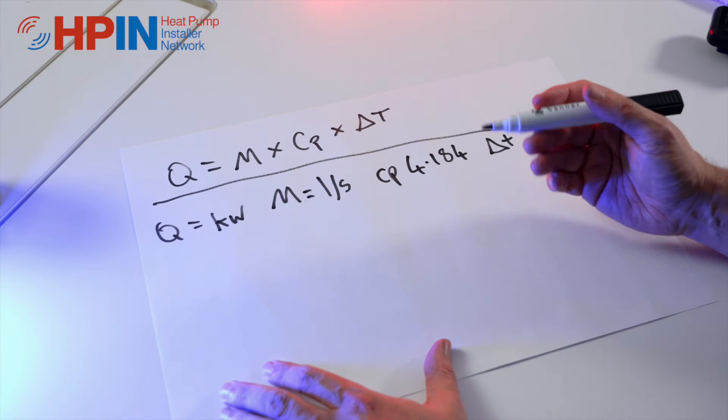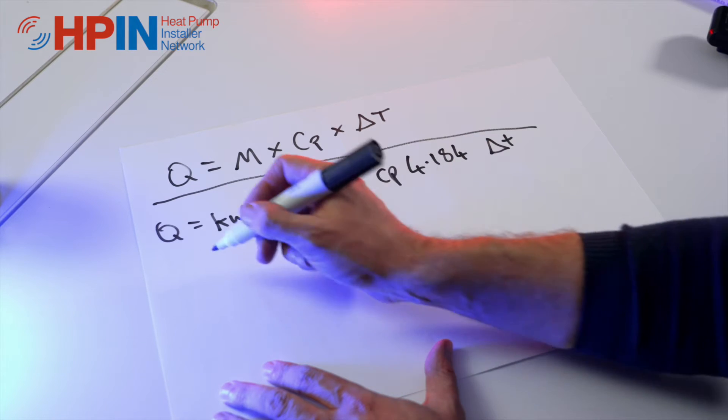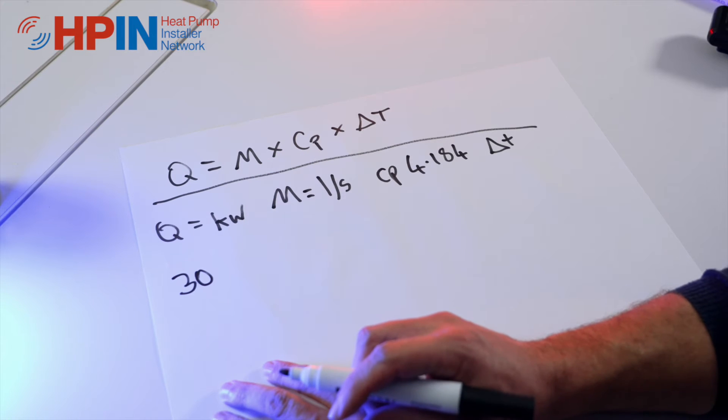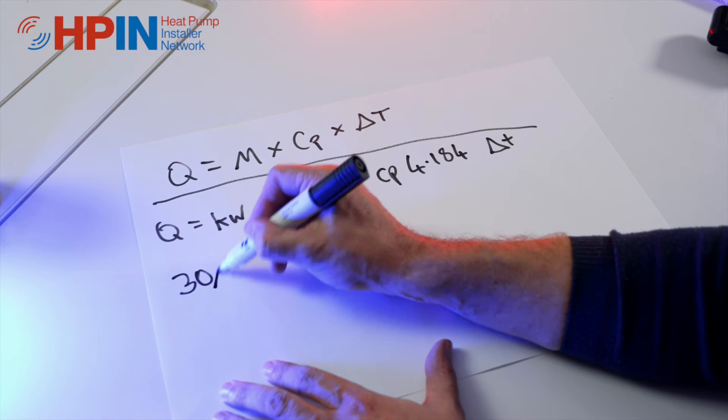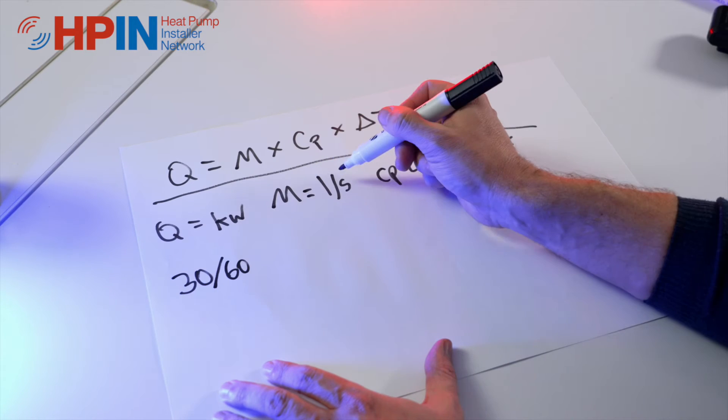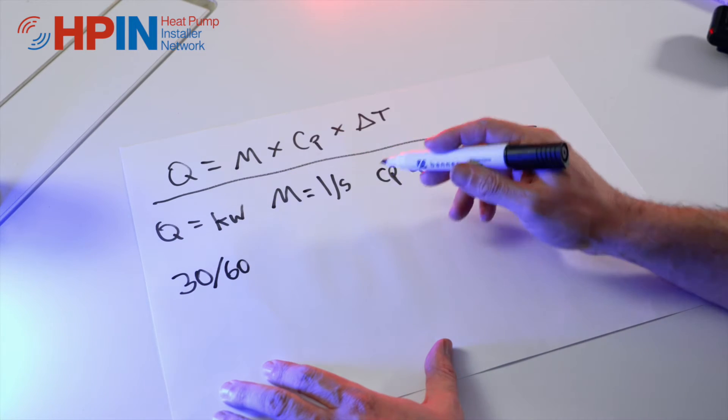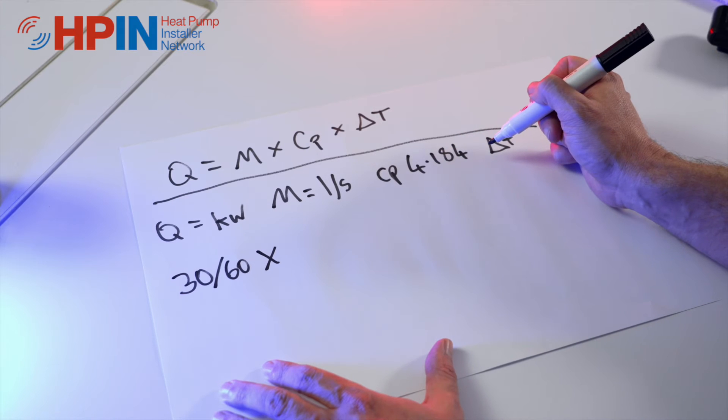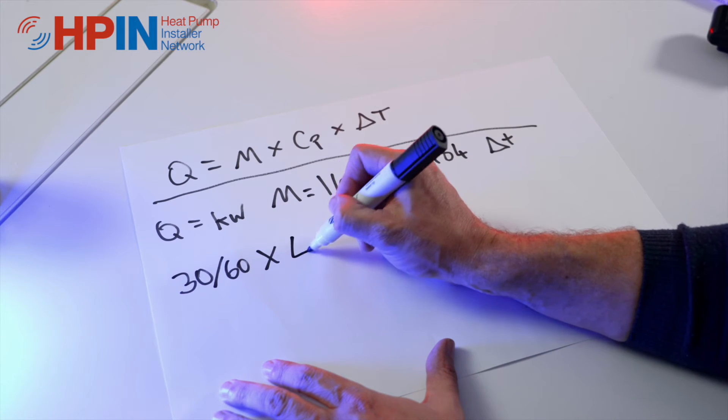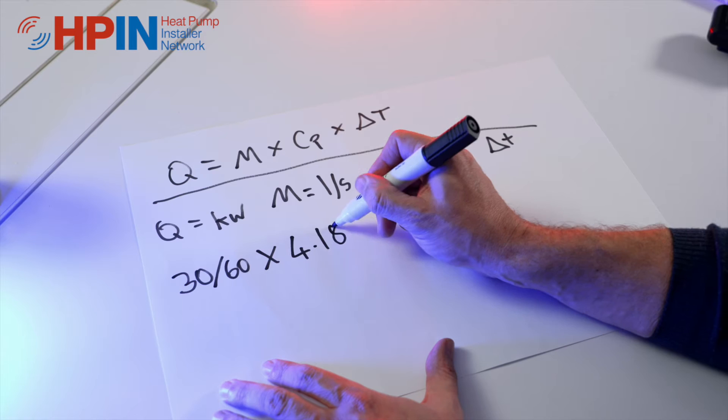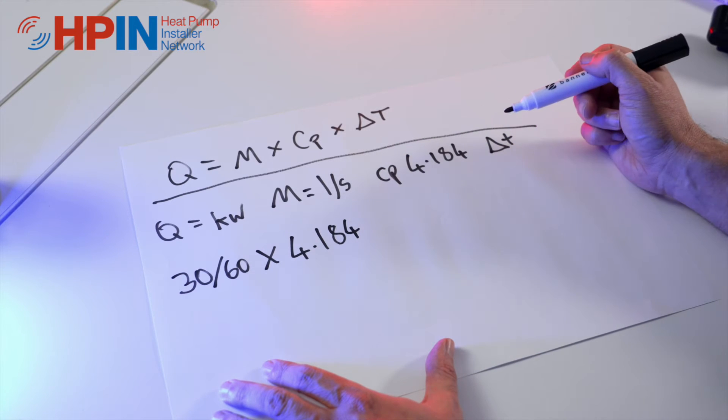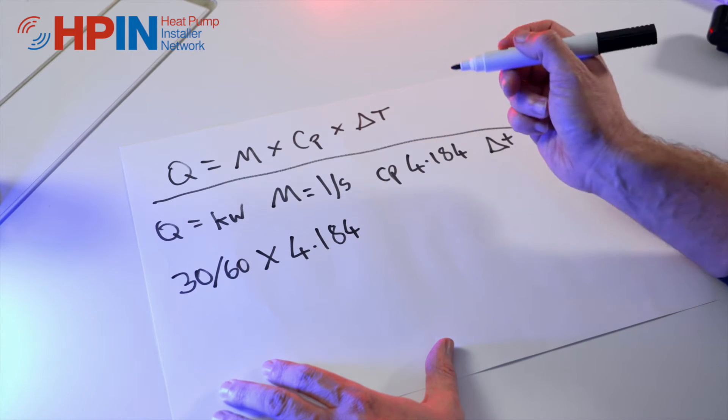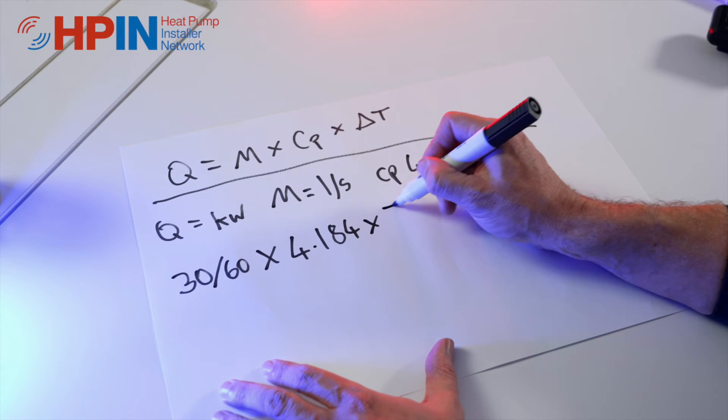To work this out and to show how important flow rates are, let's start with a 30 litre per minute flow rate. We're going to divide that by 60 because we want litres per second to make this equation work. We're going to times that by our specific heat capacity of water, 4.184. And then for this demonstration, let's say we're using underfloor heating and we've got a delta T of 5 degrees.